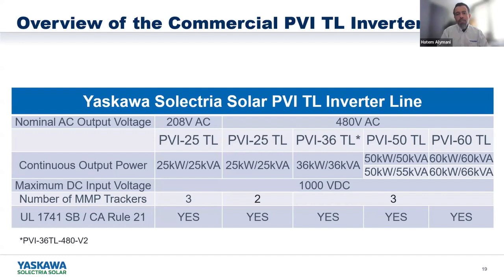Also, we have 480 volt AC, and we have the 25, 36, 50, and 60. Different from the size of the inverter, we also have the top two, 50 and 60s. Those are the only two models that come with a reactive power overhead. Some utilities will require overhead for reactive power at some times, and if you don't have an overhead, then the reactive power could eat into the nameplate rating. And as you know, our customers and all the end users, they only get paid for kilowatt hours. And when you're introducing reactive power, you're not going to get paid for that. So that's why we have those two models with an overhead. So even if the utility is requesting overhead reactive power, you can just provide that to the utility without reducing anything of your nameplate rating.